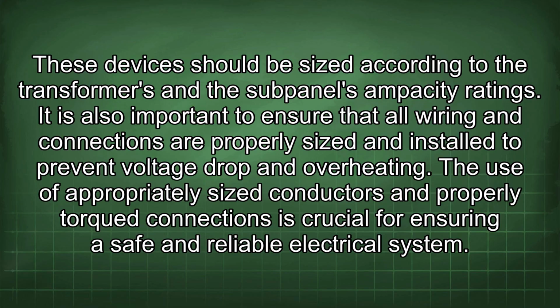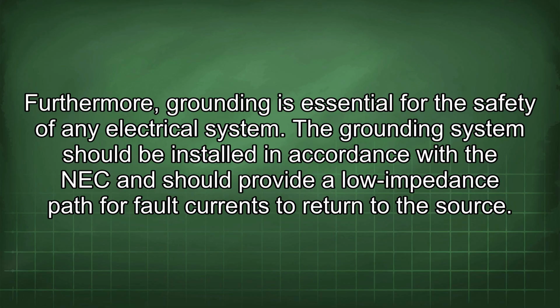It is also important to ensure that all wiring and connections are properly sized and installed to prevent voltage drop and overheating. The use of appropriately sized conductors and properly torqued connections is crucial for ensuring a safe and reliable electrical system. Furthermore, grounding is essential for the safety of any electrical system. The grounding system should be installed in accordance with the NEC and should provide a low impedance path for fault currents to return to the source.